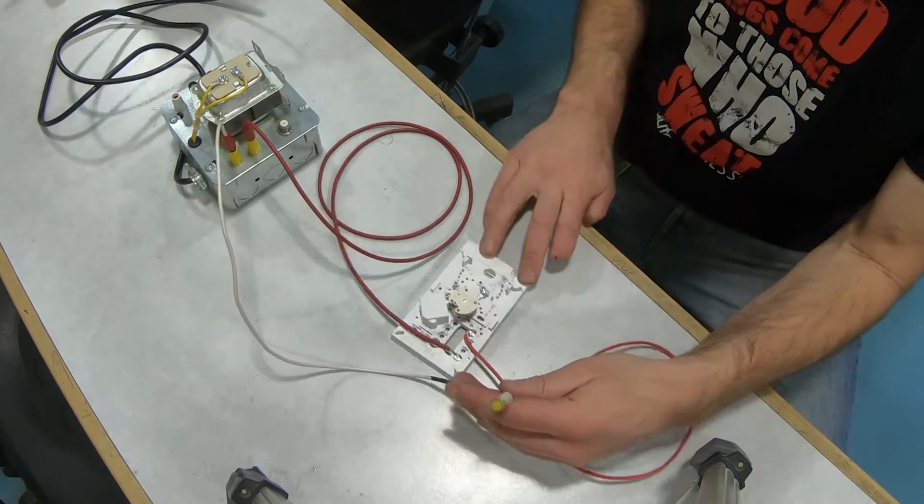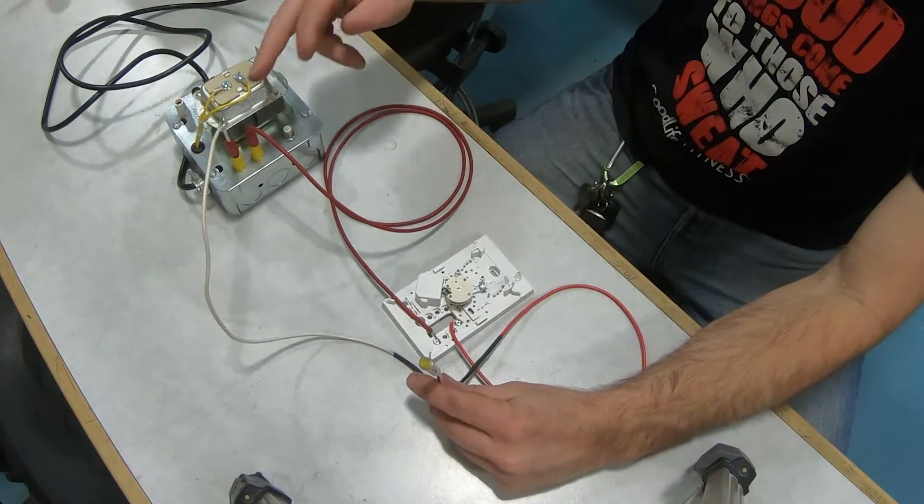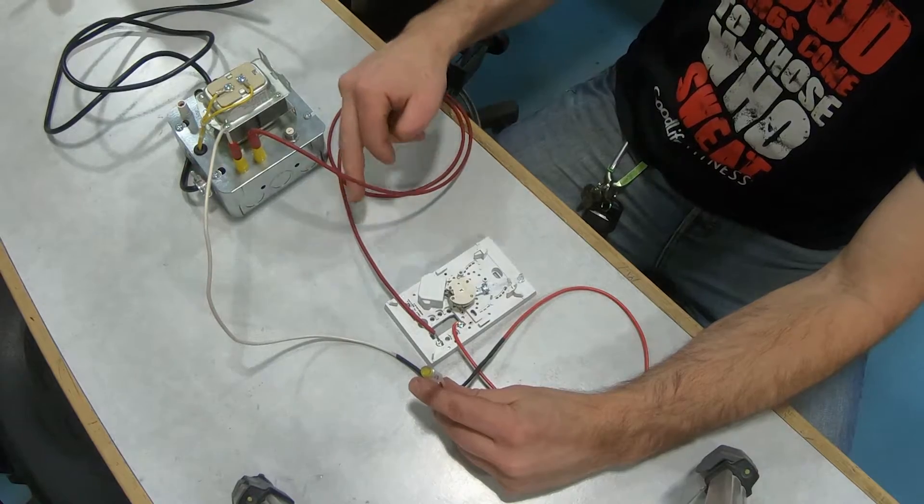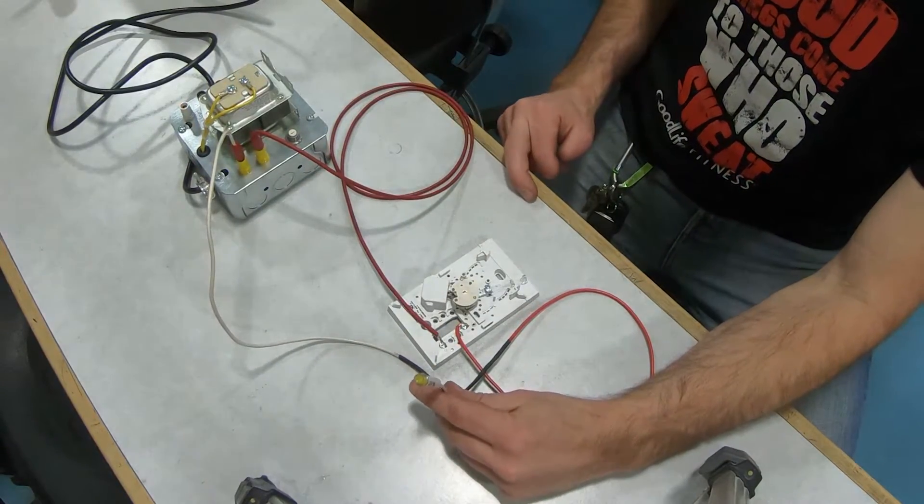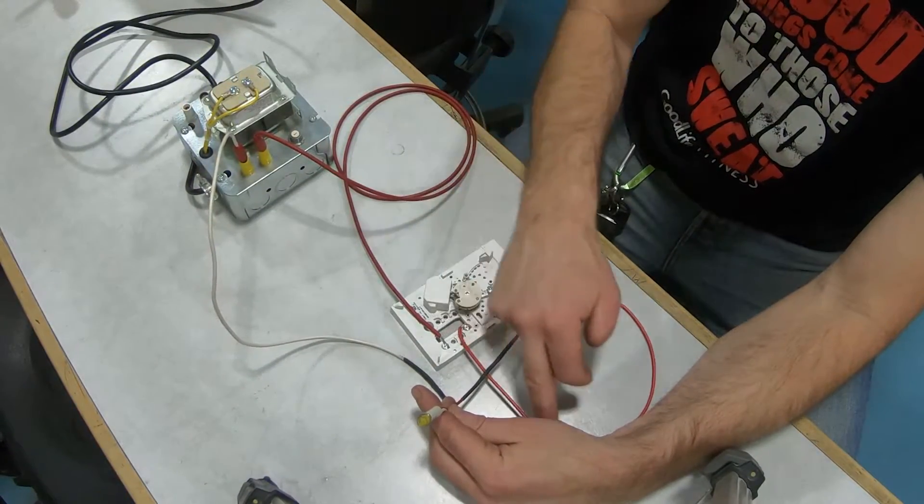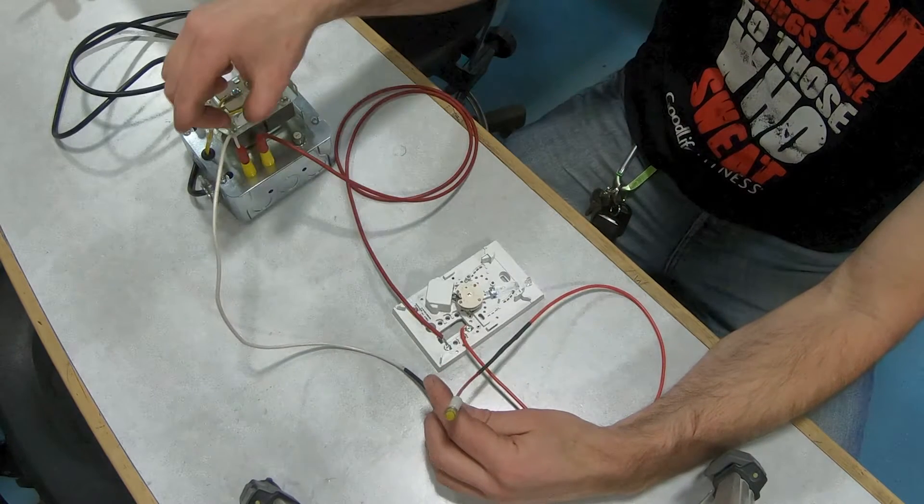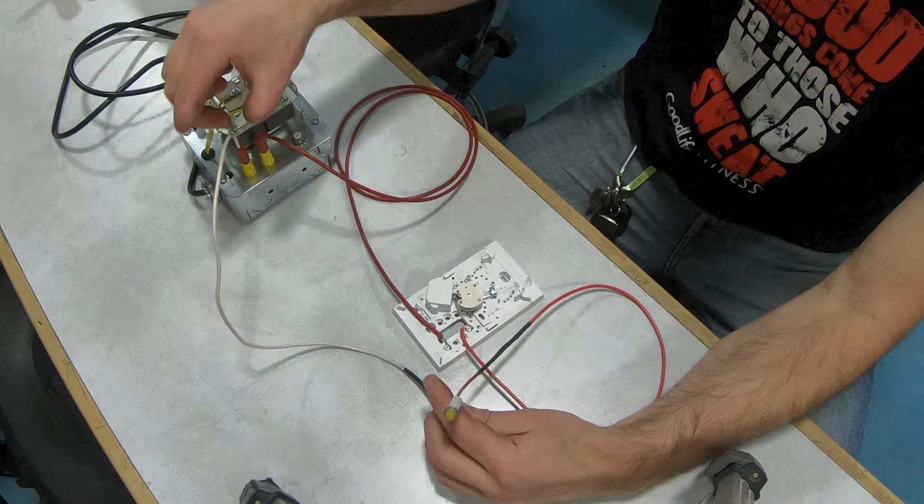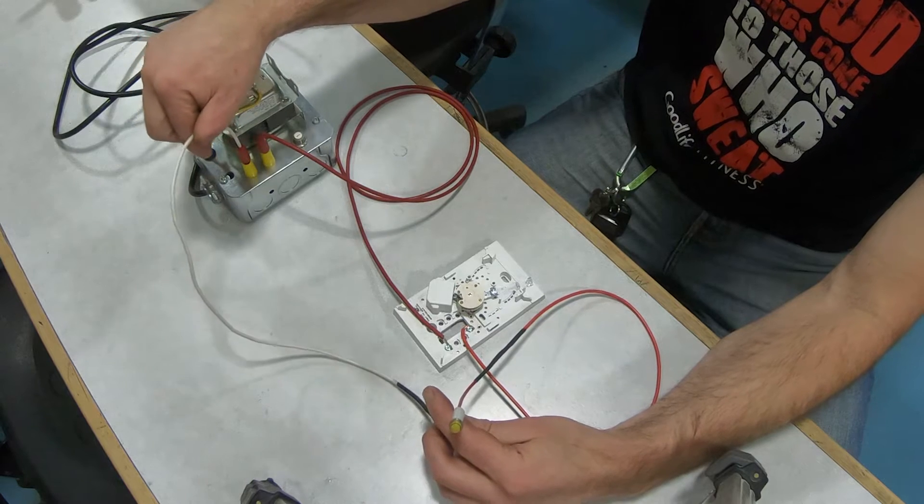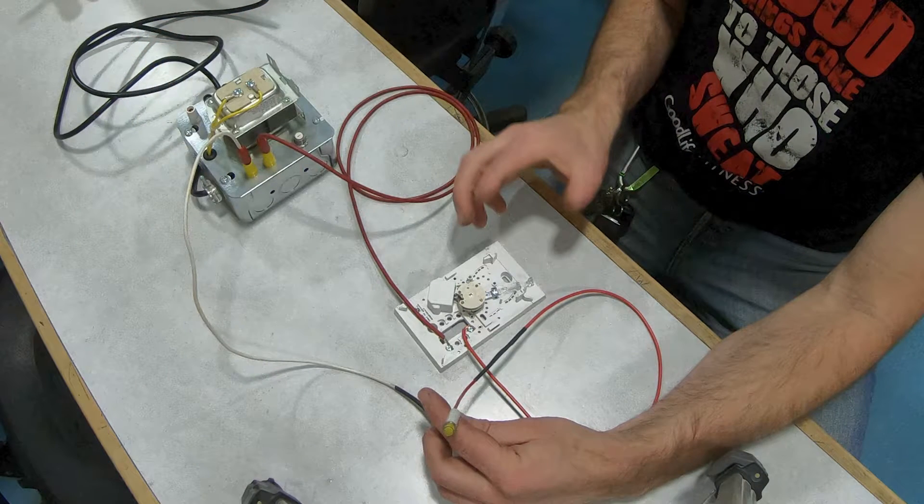In order to demonstrate this, I've made a little setup here. I've got a 24-volt transformer with a power lead going off to the thermostat. On the other side of the thermostat, a power lead goes out to an LED light, and from the other side of the LED light, the power returns back to the transformer to complete the circuit.